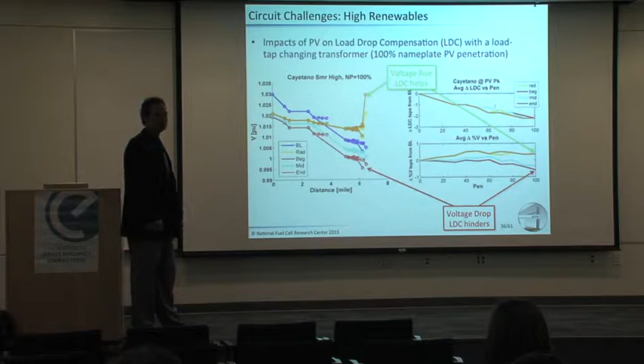It's a typical control strategy that utilities use, where they have a load tap changing transformer that, when load is high, increases the voltage at the substation, and when load is low, drops the voltage at the substation. But that leads to some problems, especially under conditions where I have a lot of solar power in the beginning of my circuit, and the load drop compensation makes my voltage drop even further than it should, going below the requirements for maintaining power to customers.